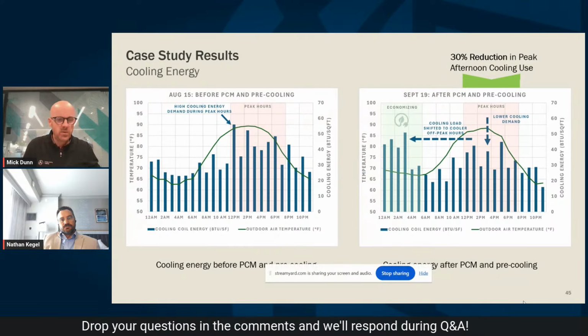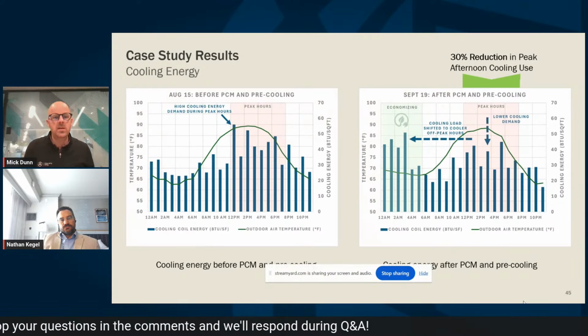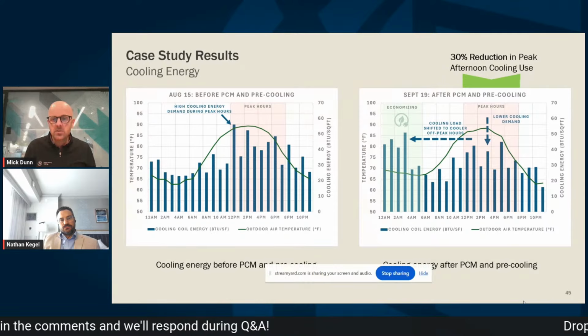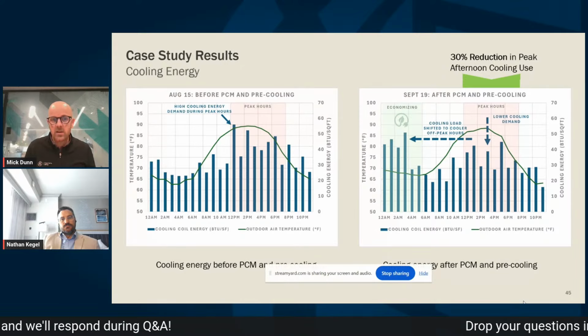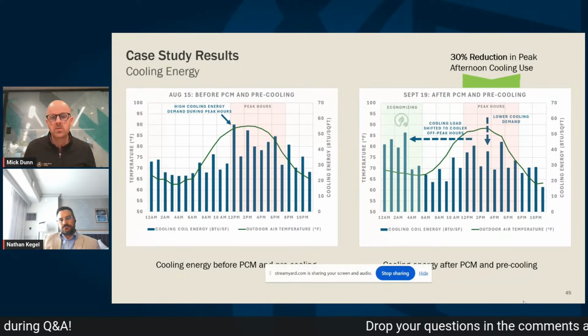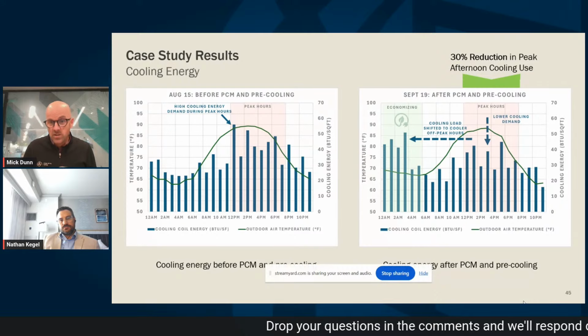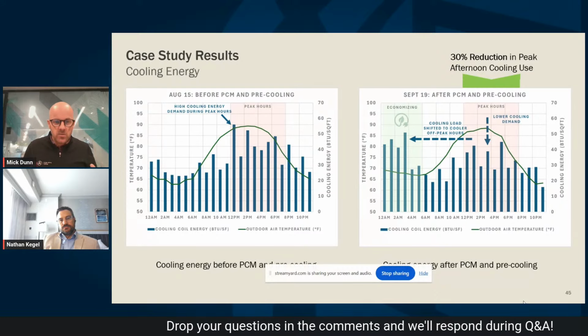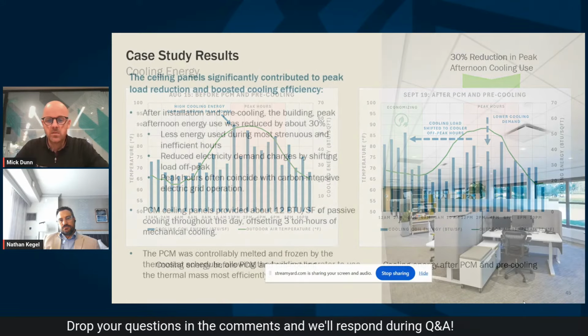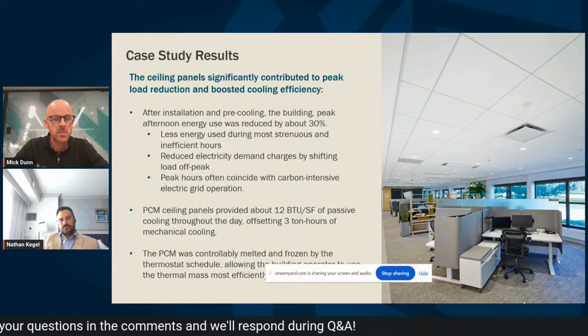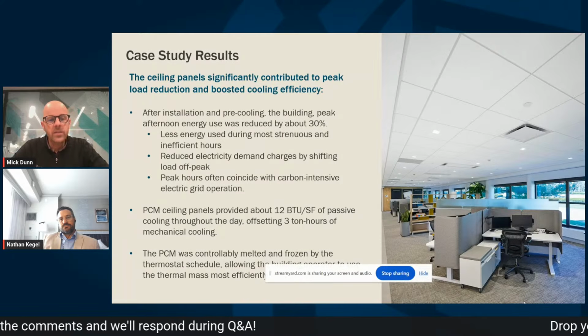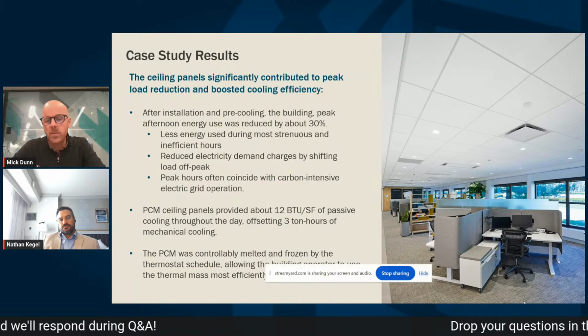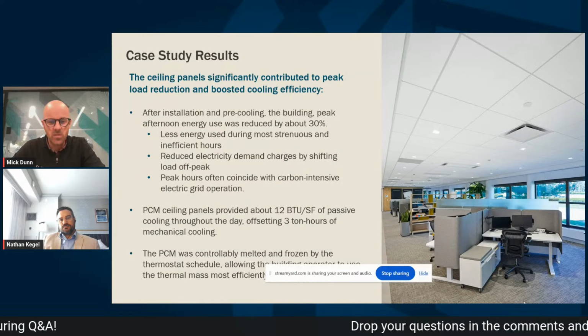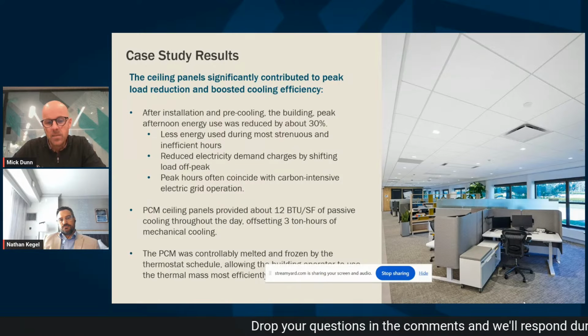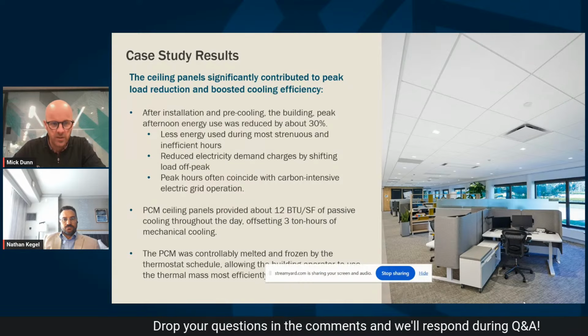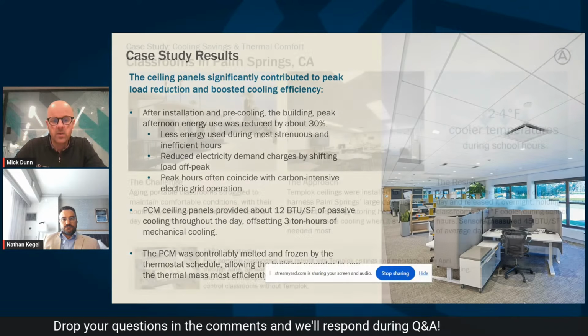And that's not to say you put this in and you get a 30% reduction in peak, but it is demonstrating that you can have significant impacts when we set up controls and really stretch that and just try to use that to validate some of our assumptions around, can this technology make a difference? So on the average, however, we're seeing around about 12 BTUs per square foot of area. So it's offsetting about 3 ton hours of mechanical cooling on the average in the area that we had installed it.